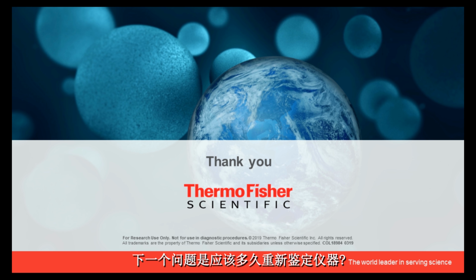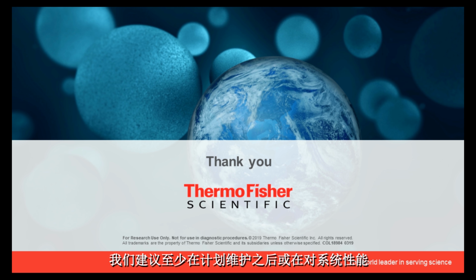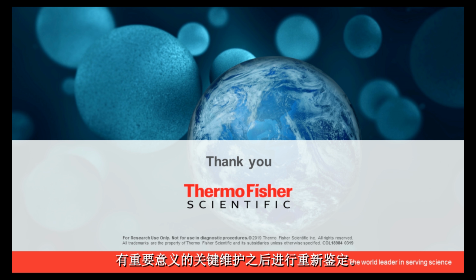Next one is, how often should I requalify an instrument? This is a risk determination by the manufacturer's recommendation and the risk tolerance of the workflow. Thermo Fisher Scientific uses that risk-based determination to make a recommendation to requalify. At minimum, for the Life Sciences Group instrumentation, we would recommend after a planned maintenance or after a critical maintenance that is significant to the performance of the system.